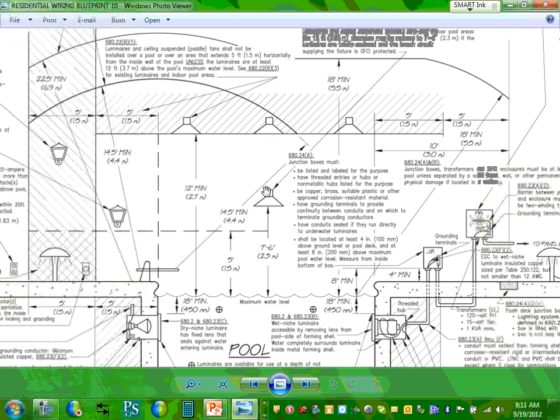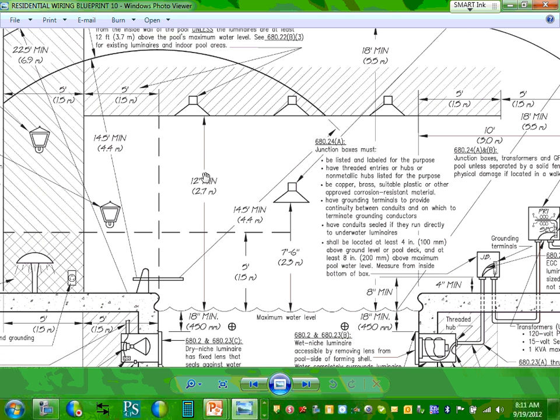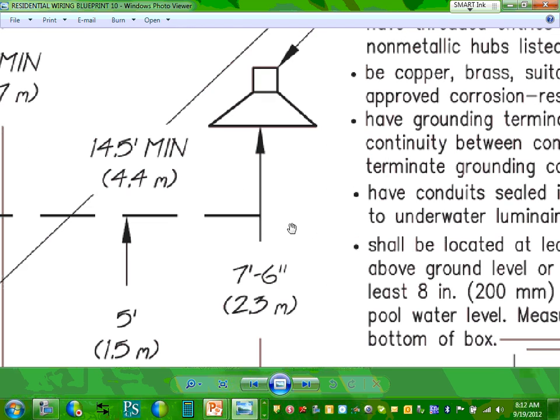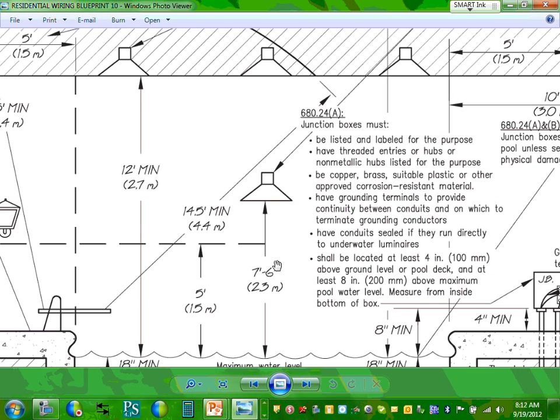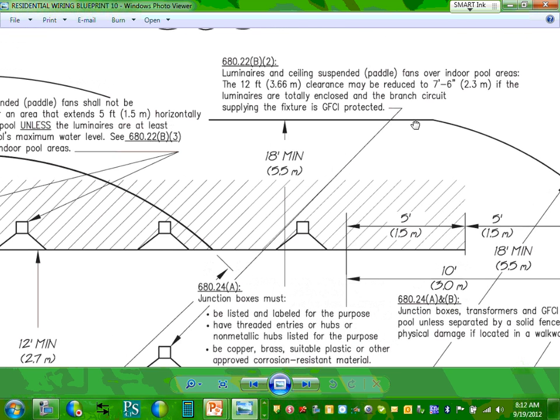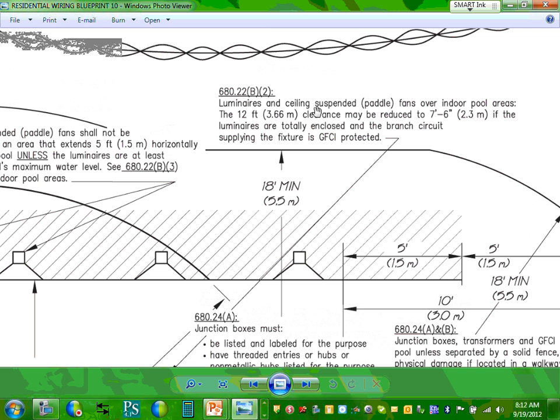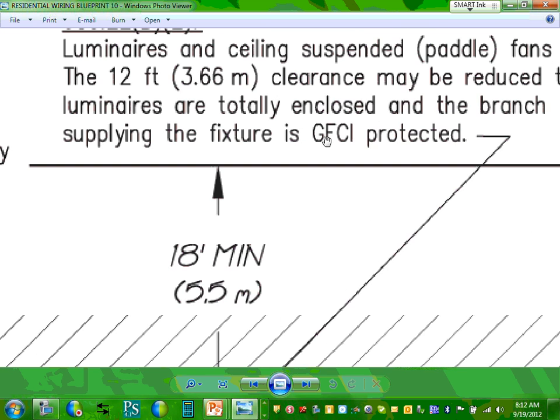Now, if you want to put a light right at the top of the swimming pool, what's the requirement? Look at this. You can put it at 12 feet minimum. So you have to go 12 feet from the water level. There's some exception for 7 feet 6 inches. Shall be listed. If you can see that requirement right here, it says luminaires and ceiling suspended paddle fans. You can put them up to 7.6. Can you guys see that magic word here? What's that magic word? You have to GFCI them. Can you guys see that here?